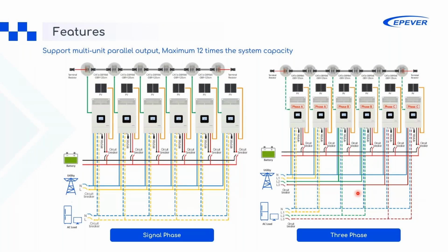And a three-phase system, this one is suitable for, of course, larger installations, because in the three-phase system inverters are divided into 3 groups, and basically they serve different phases, A, B, and C. And this configuration distributes the load evenly across 3 phases, ensuring balanced power delivery and maximum overall efficiency of the system. So we need to monitor and correct phase imbalances to avoid inefficiencies and potential system failures. Of course, the automatic phase balancing technology is embedded, but it's also important that we do not intentionally overload one phase in comparison with the others.